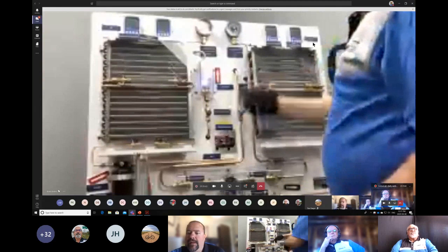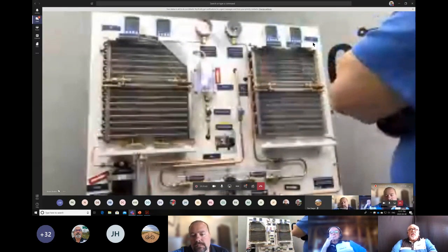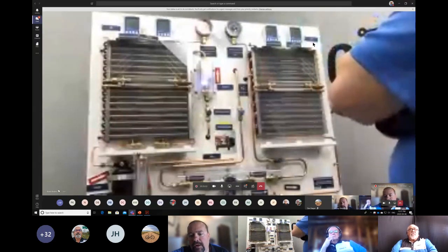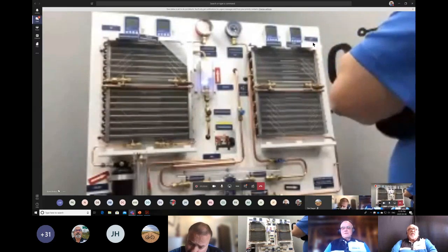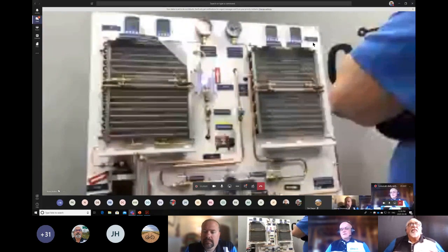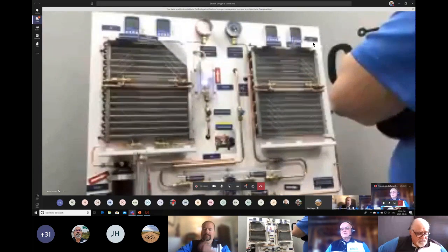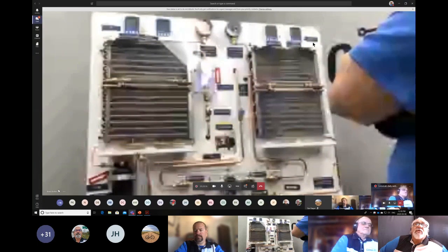Somebody asked what happens if the cabin air filter is clogged. Typically, it's going to reduce the amount of airflow over the evaporator, and you're going to see low superheat. And another question, are the numbers lower for overcharge and higher for undercharge? Yes. When you're dealing with superheat, yes. The document that I have prepared gives conditions, causes, and effects of high and low superheat and subcool, different things that will cause that. So, Kevin, what are our numbers now?